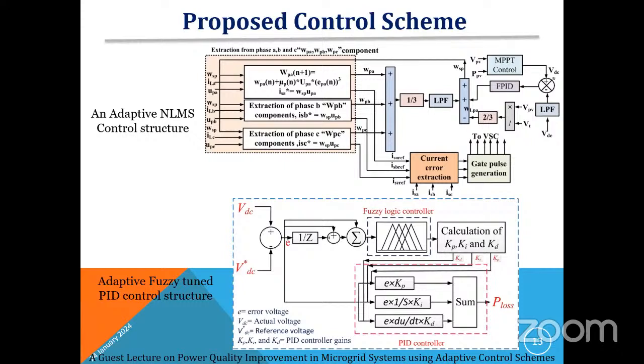So that is the reason we have to maintain the DC voltage higher than the grid voltage, approximately 1.5 times the grid voltage. That is our reference voltage. So if you are maintaining a 415 volt AC bus, you have to maintain 650 to 700 volts at the DC.